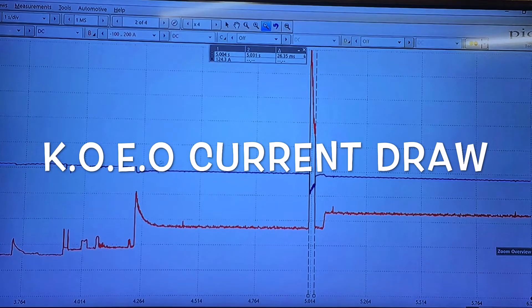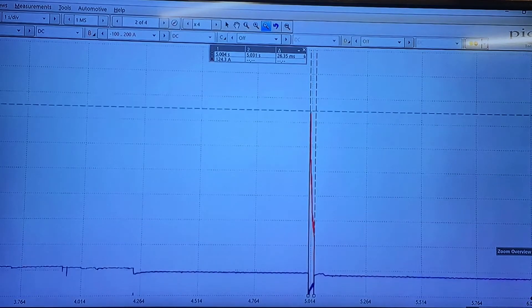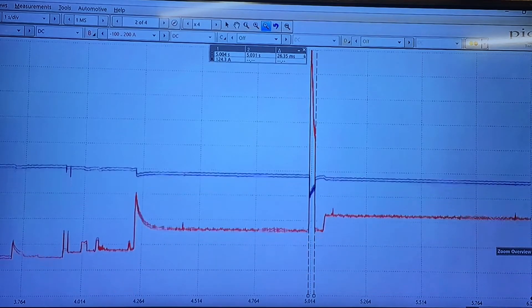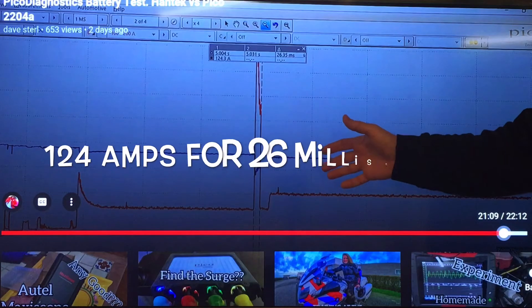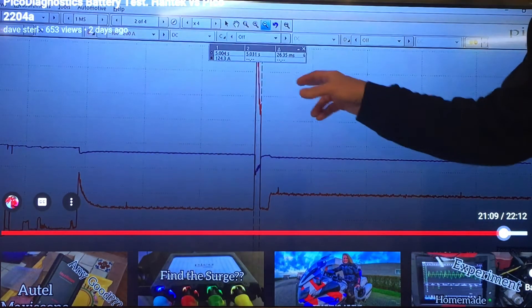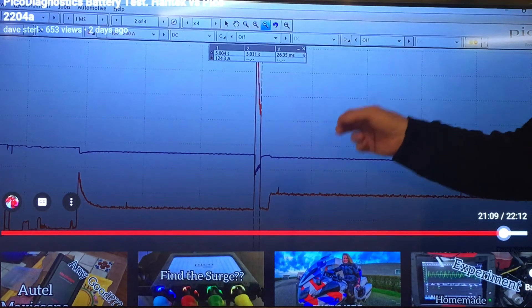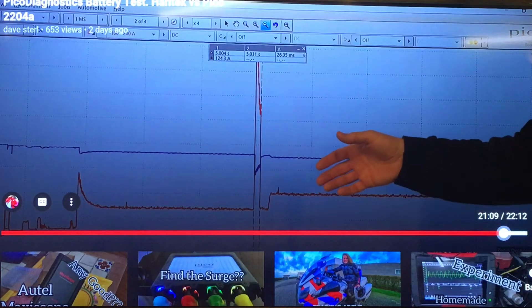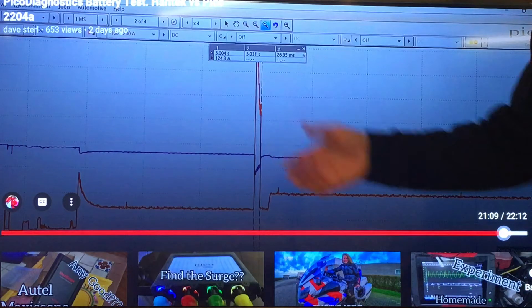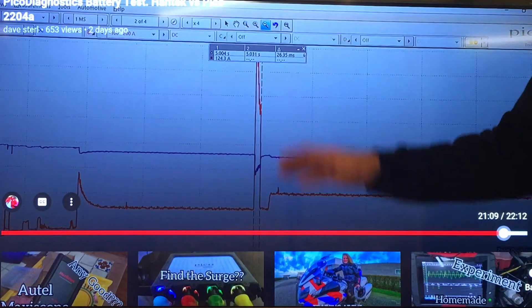Where the inrush is occurring, we have this massive spike which goes up to 124 amps right there, and it lasted for 26 milliseconds. 124 amps for 26 milliseconds. Let's call it 125 amps for 25 milliseconds to make the math easy - bastardizing these figures a wee bit, but 125 amps for 25 milliseconds.